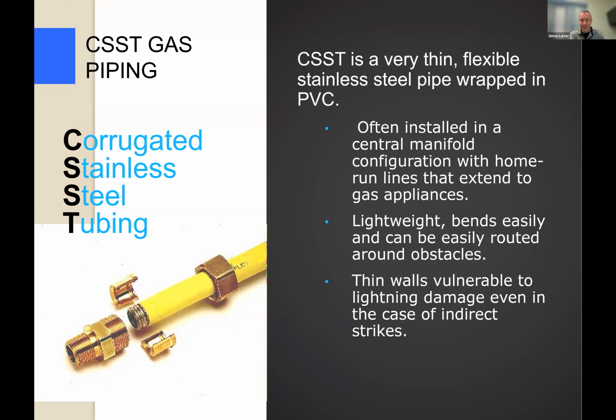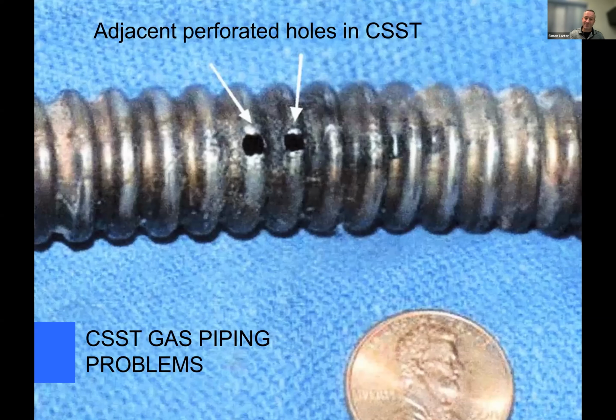The only problem is it plays terribly with lightning. If lightning goes nearby and sparks over to this stuff, it's hard to bond - it's got that rubberized coating on the outside, it's tough. We have to bond it at the manifold and at whatever appliances it's connected up to. And even if we do that, we're not guaranteed, because if lightning arcs to it, that's what happens. This stainless steel is really thin - all of the rigidity of that pipe comes from the corrugation. So it's super thin, and even a small electrical spark from lightning can cause a hole in it.